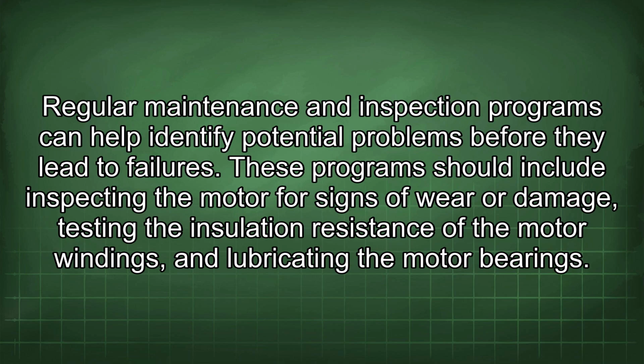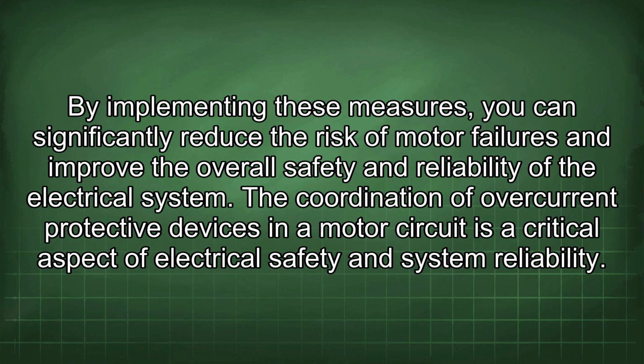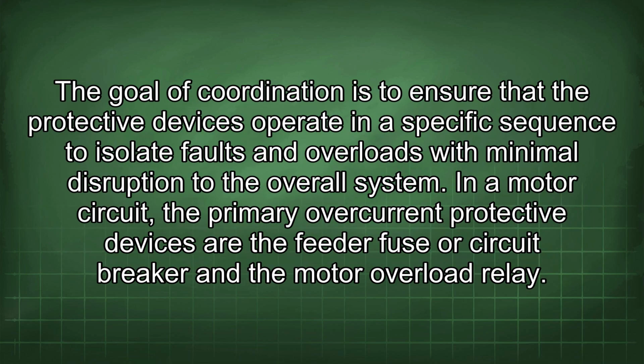Regular maintenance and inspection programs can help identify potential problems before they lead to failures. These programs should include inspecting the motor for signs of wear or damage, testing the insulation resistance of the motor windings, and lubricating the motor bearings. By implementing these measures, you can significantly reduce the risk of motor failures and improve the overall safety and reliability of the electrical system. The coordination of overcurrent protective devices in a motor circuit is a critical aspect of electrical safety and system reliability. The goal of coordination is to ensure that the protective devices operate in a specific sequence to isolate faults and overloads with minimal disruption to the overall system.